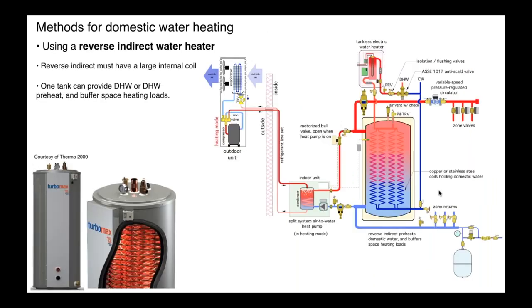Okay. Now, another option is a reverse indirect. There aren't as many reverse indirects currently on the North American market, but there are some. One example is a TurboMax tank. They've been around for quite a while. And if you're not familiar with it, basically it's a carbon steel tank with an insulated jacket. And inside there are several copper coils. If you look at that, you'll see, wow, there's a lot of copper in that. It's a lot of surface area. And that's good. High surface area means minimal delta T between the fluid that is contributing the heat to the domestic water and the domestic water temperature.